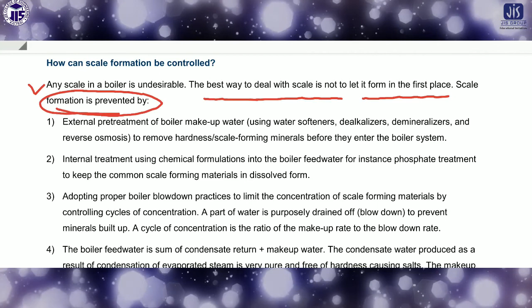By these points. External pre-treatment of boiler makeup water. When we are using the water, before utilization of the water in the boiler, we have to treat the water. The pre-treatment is required such that the impurities are removed, to remove the hardness and scale forming minerals before they enter into the boiler system. Internal treatment using chemicals is also required; there may be some kinds of chemical formulations by which you can remove the scale formation in the boiler feed water, for instance phosphate treatment, to keep the common scale forming materials in dissolved form.